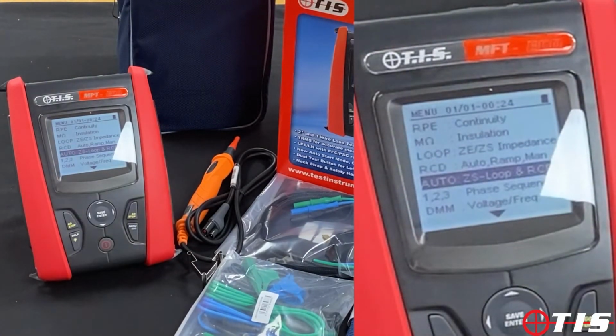As an addition, and joining together the previous 2 tests, we also have an automatic loop and RCD testing feature, where with this one it will combine live neutral, live earth, PSC, PFC tests, and all of the RCD tests, including ramp, again in one key press of the tester and one visit to the board. Again, massive time saver and obviously the added convenience.